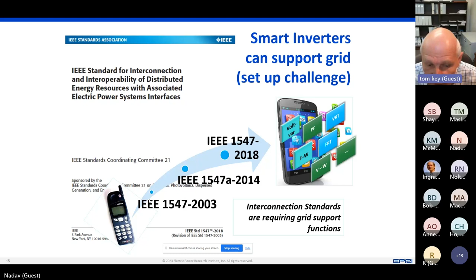I think this just goes back and generalizes a little bit the role of the standard. It clearly defines performance. I think there are 60 very specific performance requirements for the distributed energy resource, and in fact, those requirements lead to the certification of the DER. At the same time, that definition of what the DERs are doing then feeds into the technical review for interconnection that's required, how to use the flexibility that is in the inverters, and managing larger numbers of applications and higher penetrations. And it's a bit of a settlement, I think, right? Okay, we're clear on the requirements. We're learning how to do the technical review faster and better. And so there's clearly value to stakeholders all the way around.